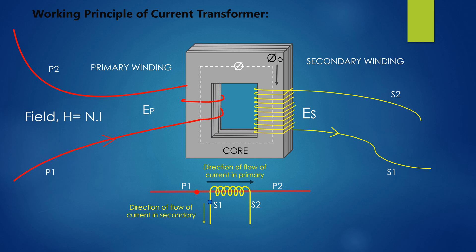The secondary windings of the CT is connected to the burden, like measuring instrument or protective relay, and become shorted. The alternating current starts flowing in the secondary winding of the CT when primary is energized. The current in secondary winding creates an opposing magnetic flux that opposes the main flux created by the primary winding. The net flux in the core equals the difference between primary and secondary flux.